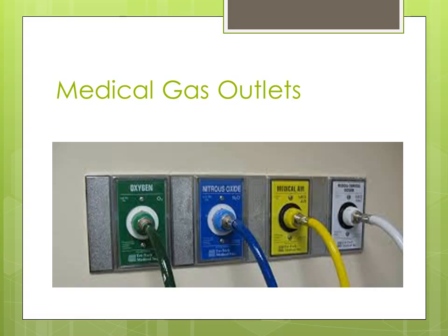And where that created problems for us is that certain equipment, particularly equipment used by respiratory therapy, if they were to take a crash cart and have to go to a different unit, they would have to keep multiple adapters or different type hoses to connect to the outlets. And you can imagine new personnel, or maybe somebody didn't put the adapter back, and so they get to a code and they need to connect something, and guess what? They can't connect. So they scramble to find an adapter or a connector, and that delay obviously could create an issue for patients. And we had a situation like that when we ended up going through and standardizing our outlets, and it took quite a while.